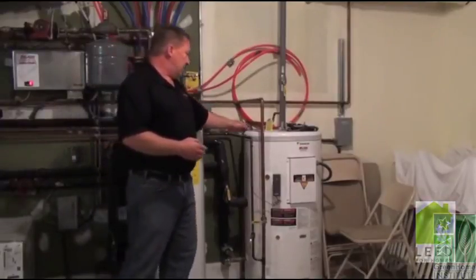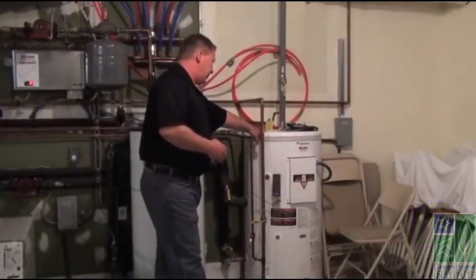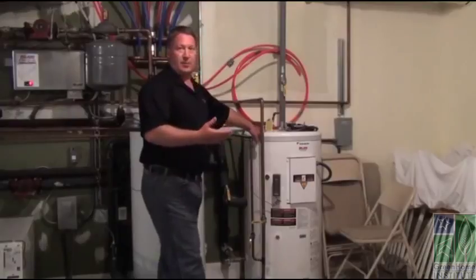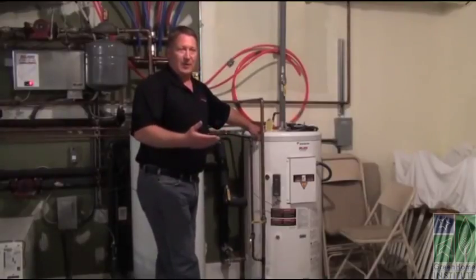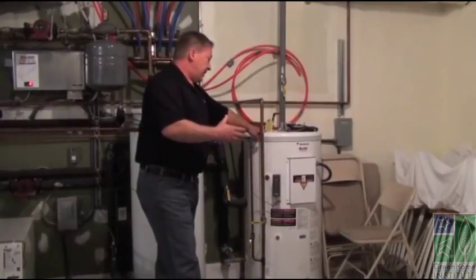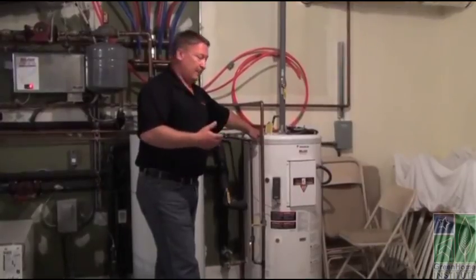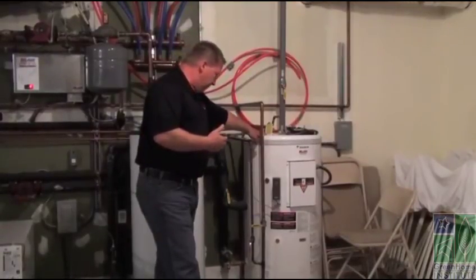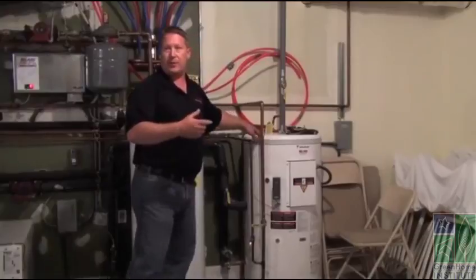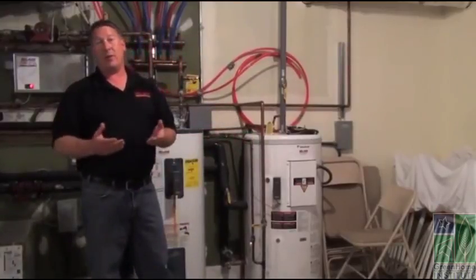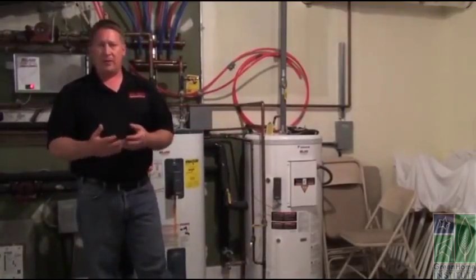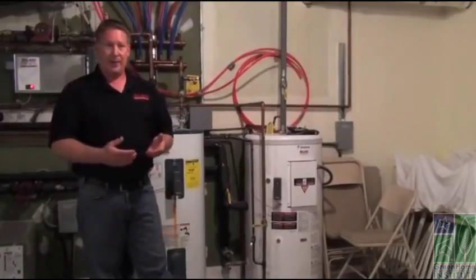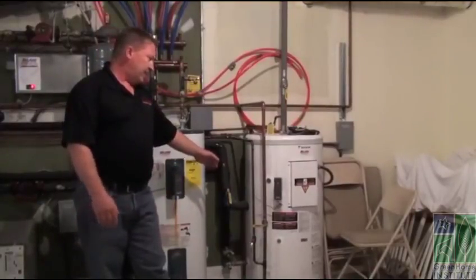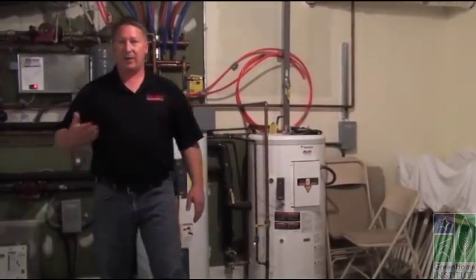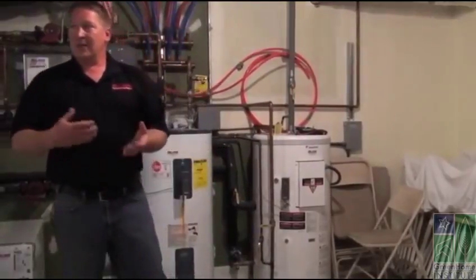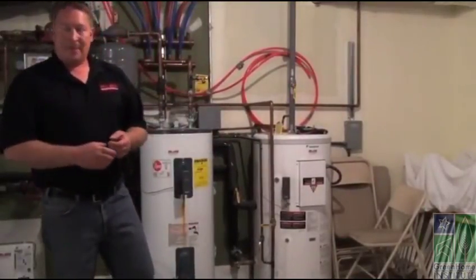This tank though does need some maintenance on it because it is not a closed system, it's a potable or domestic water system. That tank will develop sediment, and normally what I recommend is to drain the tank and stir the tank to relieve the sediment, especially on a well system where you can have some iron and buildup of things like that. To drain this on a yearly basis to make sure you get that out of the bottom of the tank to avoid it filling up with sediment.